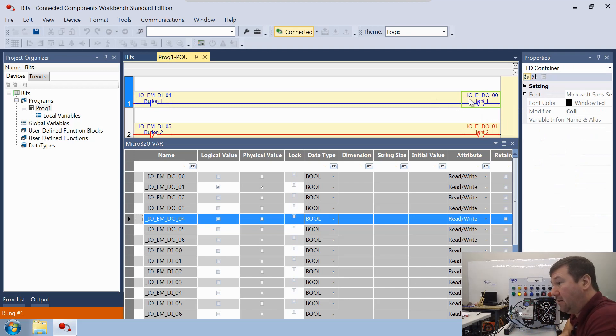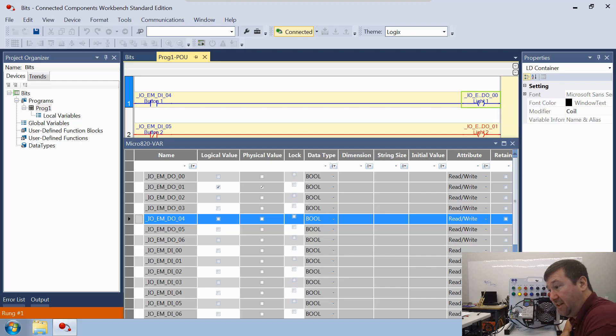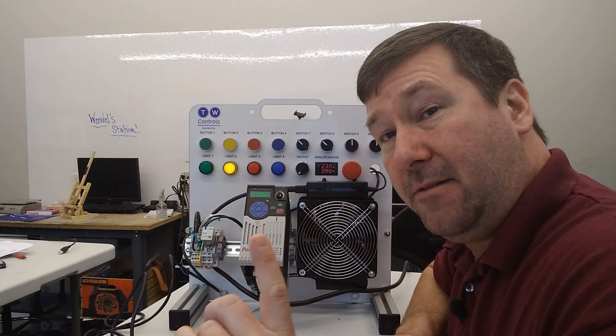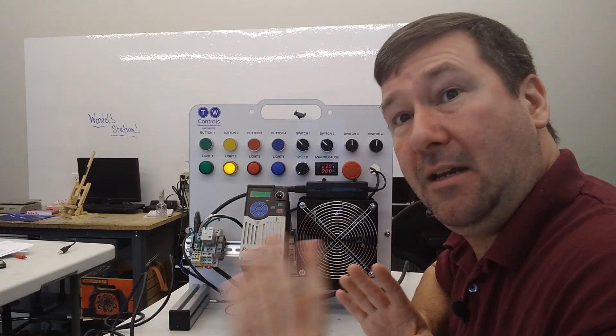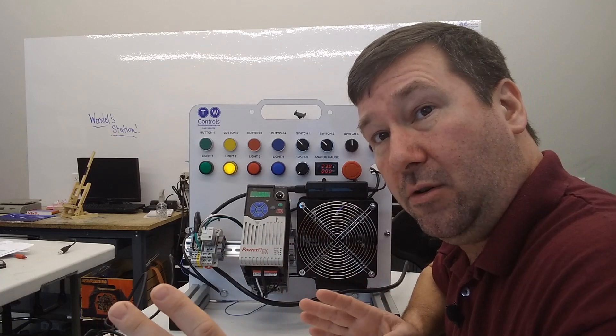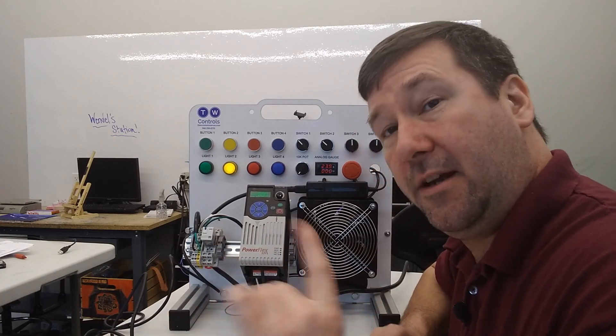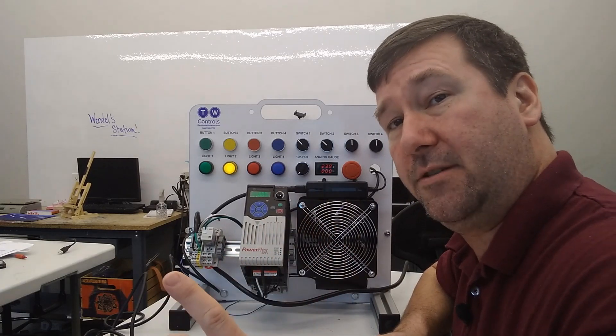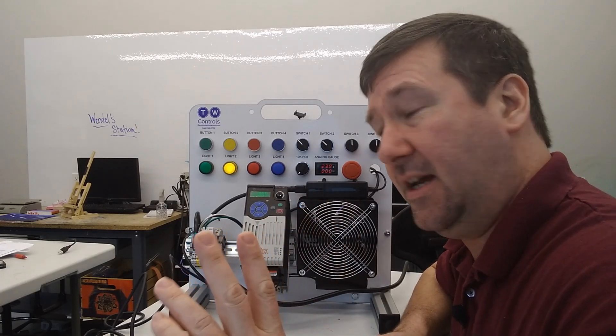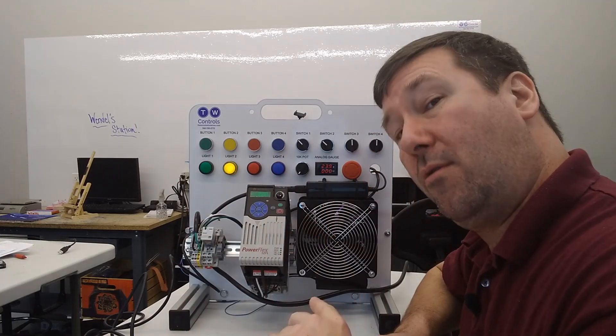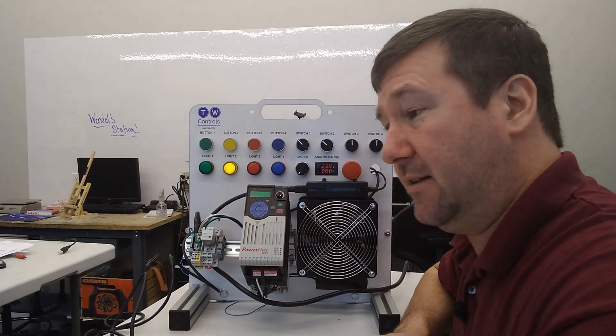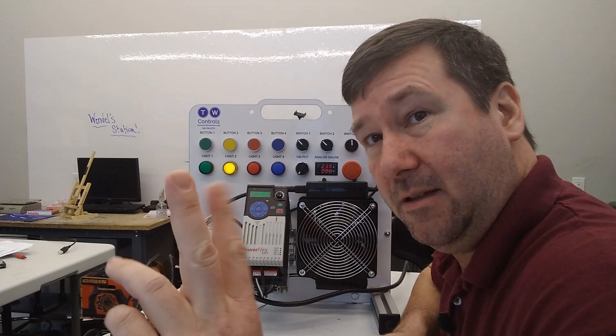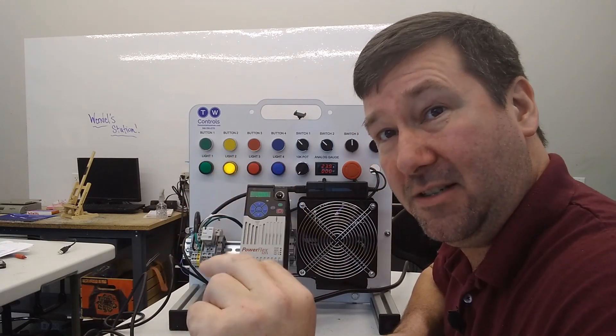This is very important. A lot of people will say a false coil or false output does nothing. No — it goes and writes a 0. It's very important to realize that every single output instruction, with few exceptions, does something whether it's true or false. Almost none of them do nothing. And yes, if you've seen my latch-unlatch video, that's the big one where one of them does nothing.